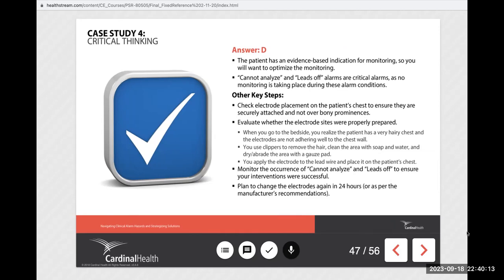Cannot analyze and leads off alarms are critical alarms, as no monitoring is taking place during these alarm conditions. So, what steps should you take? Check electrode placement on the patient's chest to ensure they are securely attached and not over bony prominences. Evaluate whether the electrode sites were properly prepared.